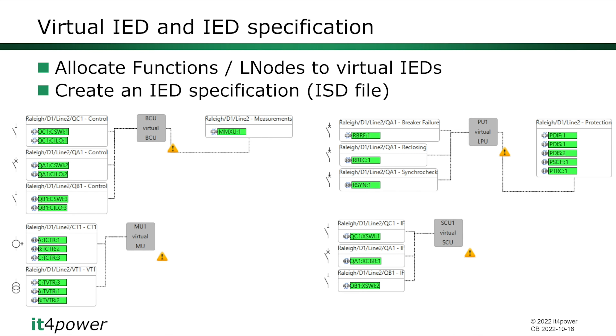This can then be used as a specification towards an IED vendor, and the vendor, based on that, can return an ICD file that fulfills these requirements. With that, you also have a way to verify, in a machine-based manner, whether what is proposed by the supplier corresponds to what you expect as a utility or user requirement.